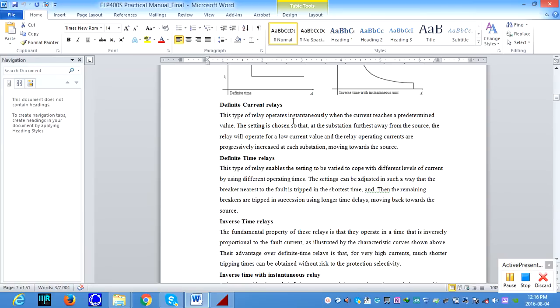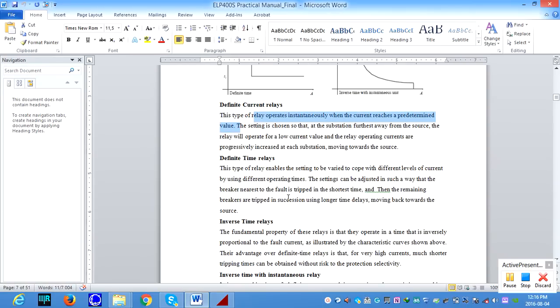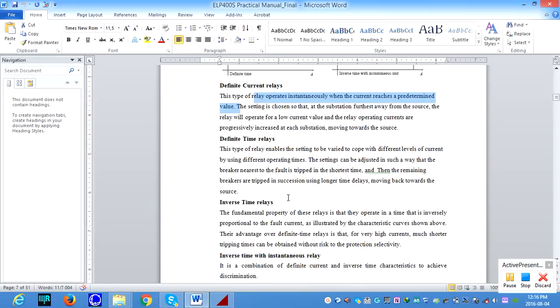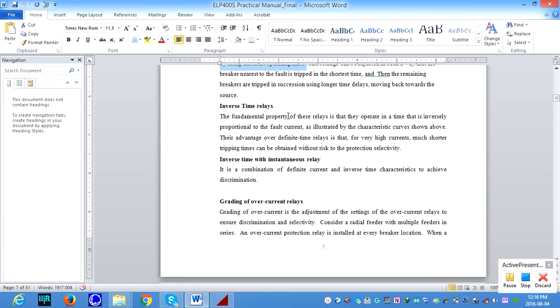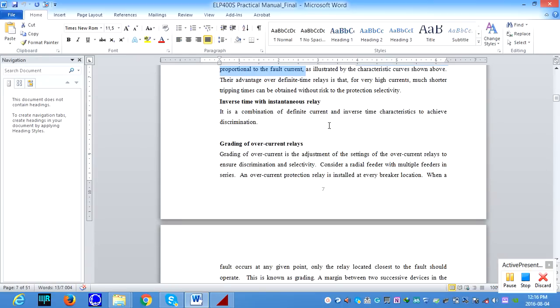For definite current, the setting means the relay operates instantaneously when the current reaches the predefined value. That's the definition for the definite current. And for the definite time, we are saying the relay enables the setting to be varied to cope with different levels of current using the operating times. And for inverse time, the definition is illustrated here. The relay operates in a time that is inversely proportional to the fault current. And inverse time with instantaneous is basically a combination of definite and inverse characteristics.